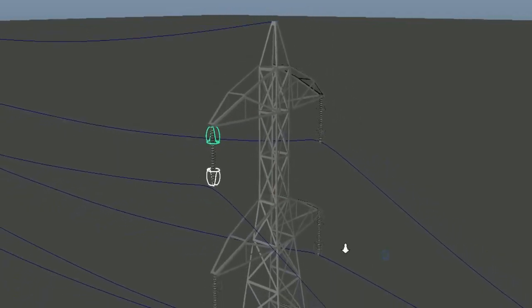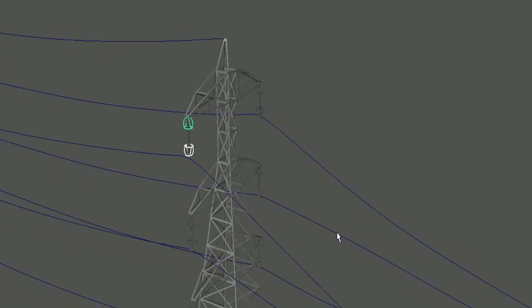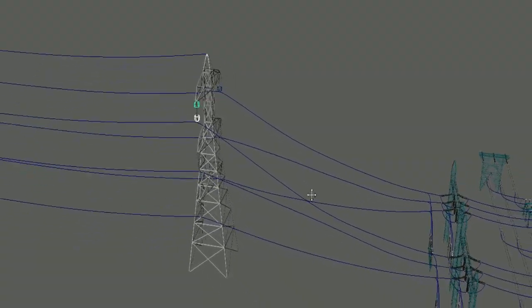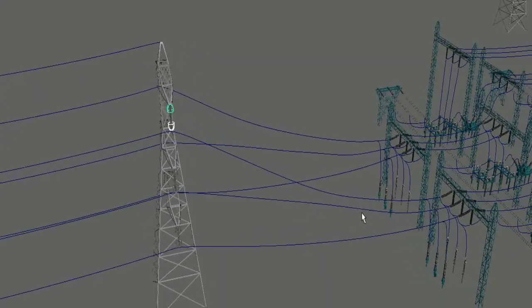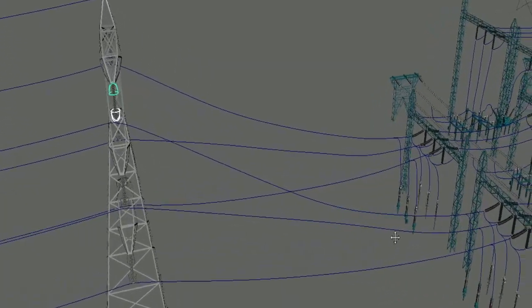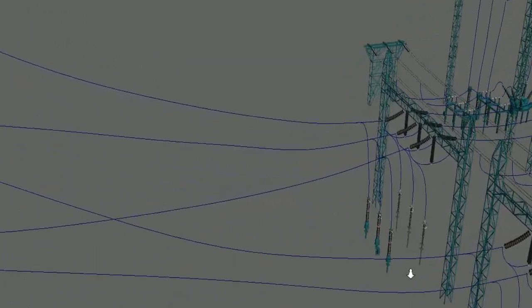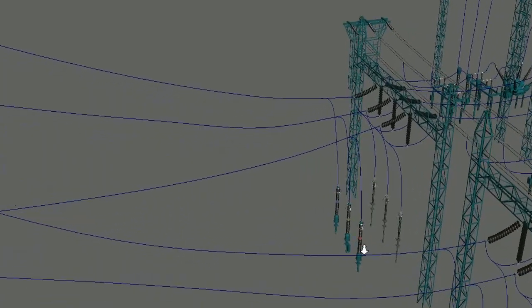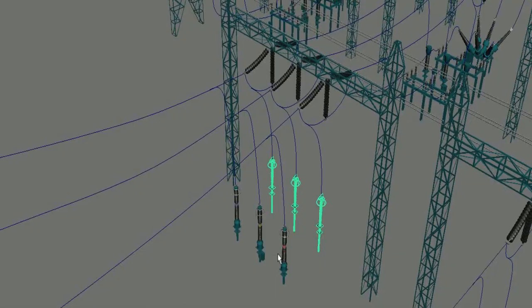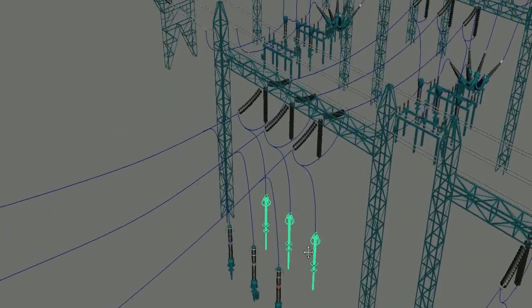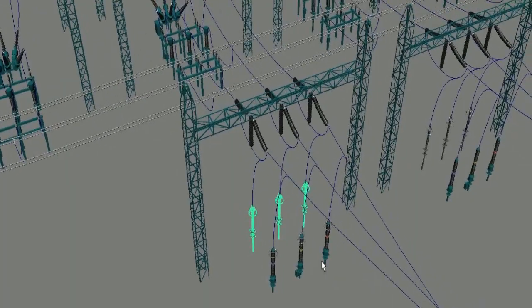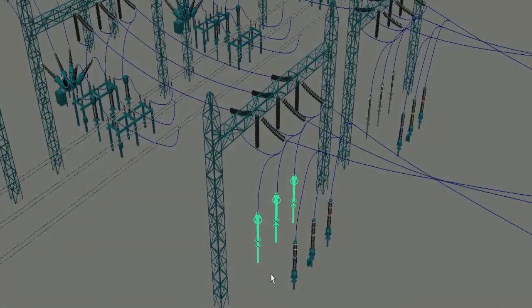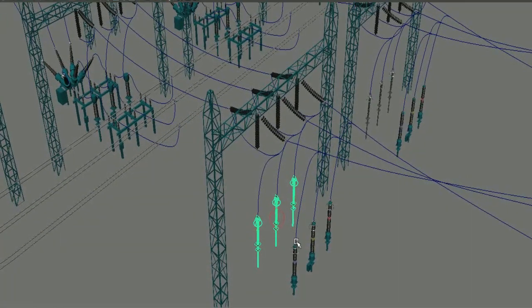However, the voltage spikes travel very rapidly through the transmission line and could reach up to the electrical substation. To avoid them reaching into the substation, the surge arrestors are installed in parallel to each line conductor at the entry point.